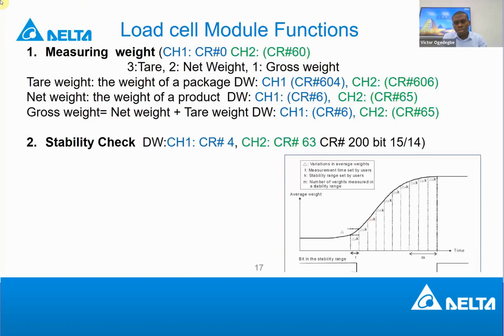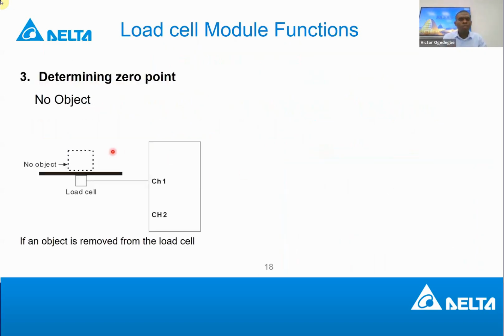Then if we go back to our presentation, on the other hand, if the range, you see now the range has exceeded, it's like overshooting, and then the bit goes low. So bit 14 for channel 1 is low. So it means that what is being measured now is not stable. It's out of the range you have specified on this register that you take as a stable range for your machine. Stability check, that is the second function.